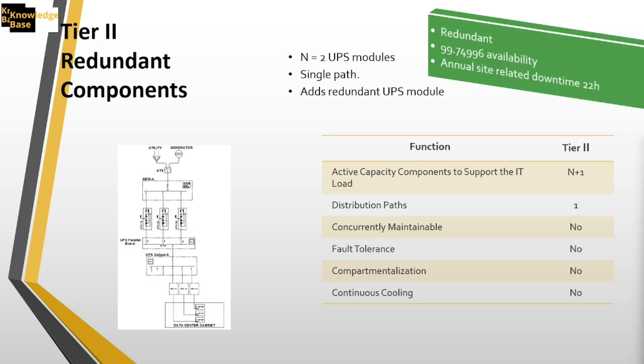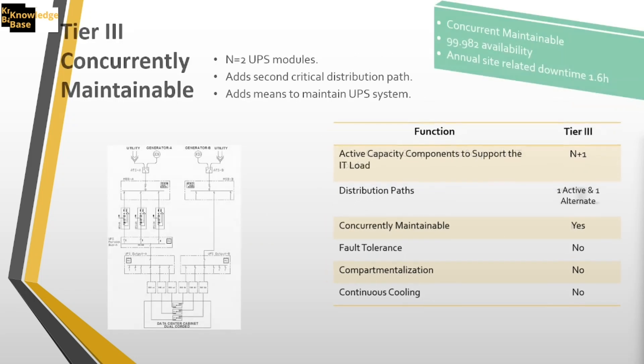Keep in mind that redundancy should be similar across all three main components of a data center to maintain the tier level. In tier 3, a concurrently maintainable data center, it's not only about redundancy in capacity — we also need a diversified path. We have redundancy in the power system on one end and a diversified path from another source on the other end, so there is no single point of failure all the way up to the rack. There are separate utility sources, two different generators, all coming through different automatic transfer switches to the rack.